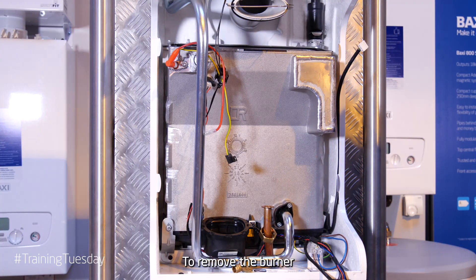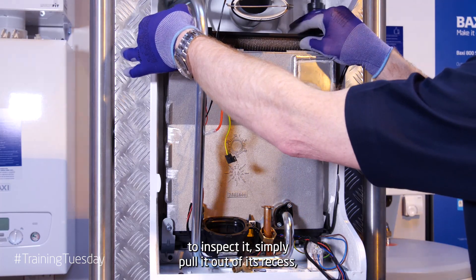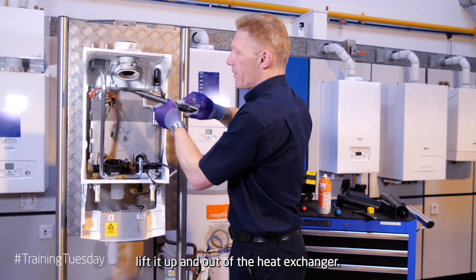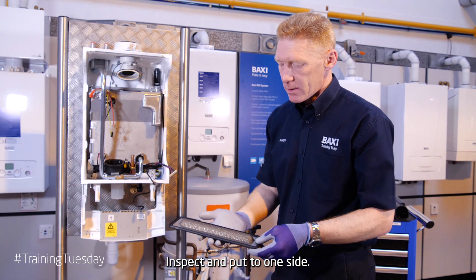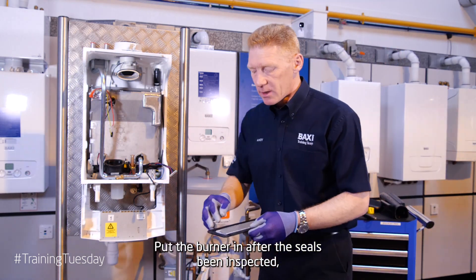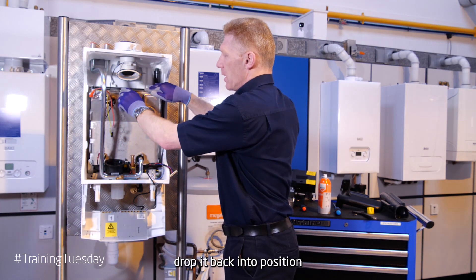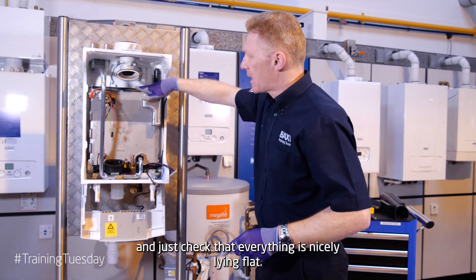To remove the burner and inspect it, simply pull it out of its recess. Lift it up and out of the heat exchanger. Put to one side. When putting the burner back in after the seal has been inspected, drop it back into position and just check that everything is nicely lying flat.